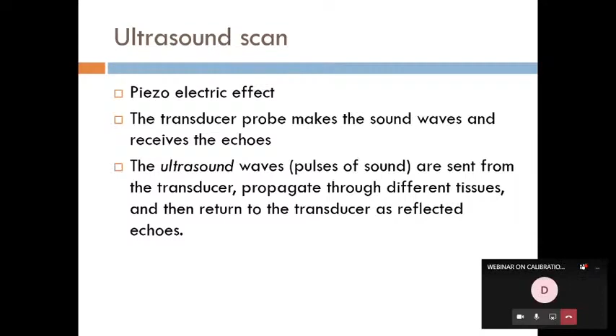This is a typical ultrasonic machine block diagram. There is a storage device, CPU, printer, and the transducer probe. With the help of the transducer probe, you can get the image. At the tip of the transducer, there are piezoelectric crystals. These piezoelectric crystals vibrate and produce sound. That sound energy travels into the human body and comes back as an echo. The echoes are absorbed by the transducer and converted. The main principle is: the higher the frequency, the lower the penetration. With high frequency probes, you get lower penetration.